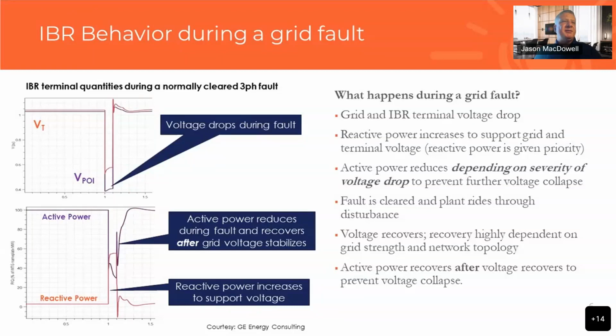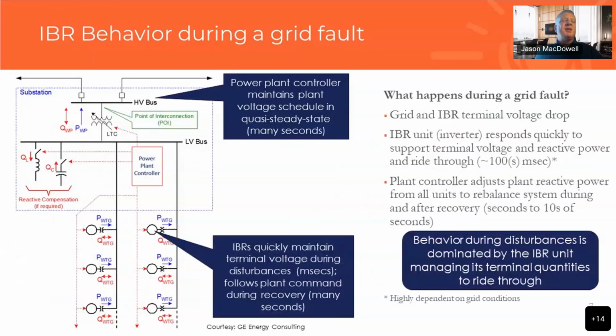And then as soon as that fault clears, the active power will recover, but only after the voltage recovers. We don't want to push watts through an unhealthy voltage, or a voltage that hasn't fully recovered. So that's one of the things I wanted to point out. And there's opportunity to harmonize with some of the language in PRC 24 and IEEE 2800 that I'll share in a minute. The other aspect is maintaining facility voltage, maintaining a voltage schedule.